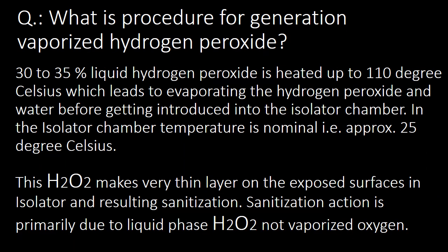The next important question: what is the procedure for generation of vaporized hydrogen peroxide? 30 to 35 percent liquid hydrogen peroxide is heated up to 110°C, which leads to evaporation of hydrogen peroxide and water before getting introduced into the isolator chamber. Inside the chamber, the temperature is nominal — approximately 25°C.